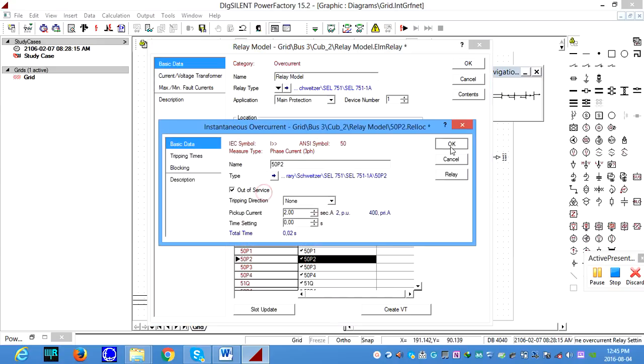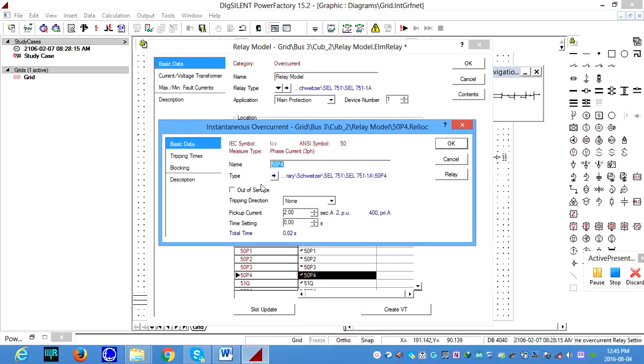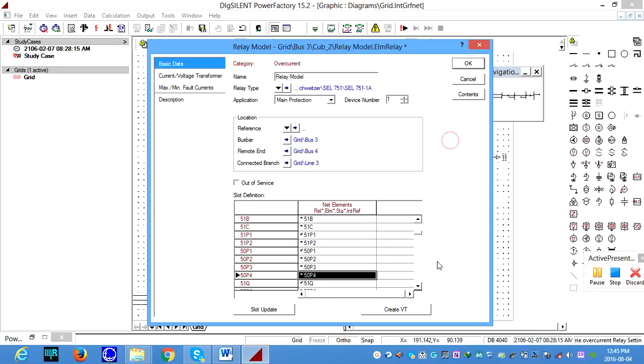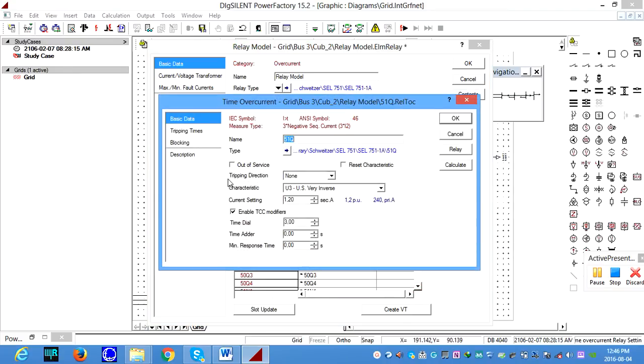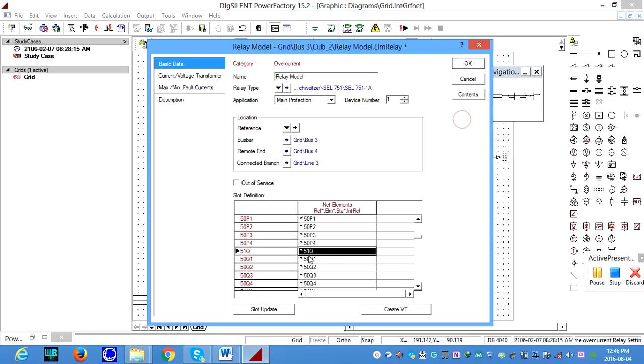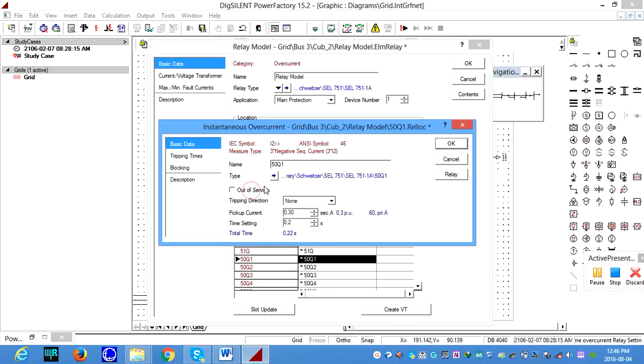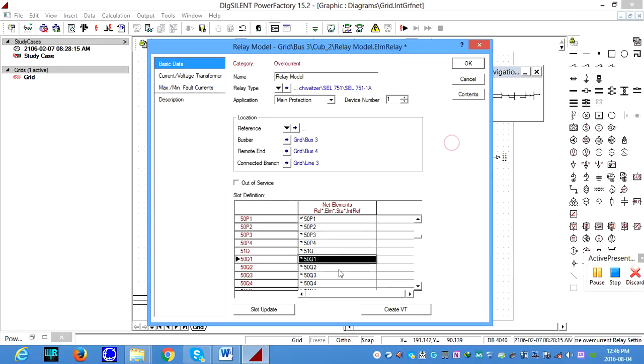50P2 is not in service. 50P3 is not in service. 50P4 is not in service, because it provides you stage 1, stage 2, stage 3, stage 4. But we are only considering stage 1 in this case. So we removed everything. And also we want to make sure the other elements, like the Q, are not in service. So it's ANSI standard. We remove them out of service. Okay, we remove them out of service. So it's already out of service. That's good.